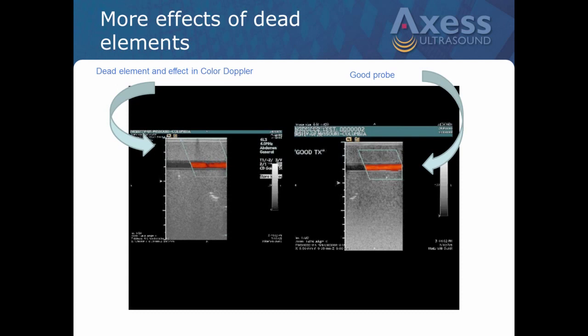A question from Valentine: will any crack on the probe definitely cause it to be dead? If I understand the question -- maybe you mean if you drop it or something like that -- it can. We see a lot of probes come into our facility where you can definitely tell it was dropped, because a whole series of elements will be dead, almost as if someone took a block and cut a chunk out of it. We can see that with some of our test equipment. That doesn't mean every time you drop a probe it's going to crack and cause a problem, so it's just a matter of having it tested if something like that happens. But if the element is cracked, it's dead -- there's no repairing it.